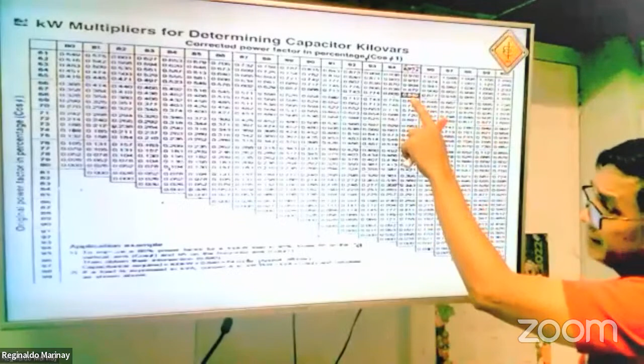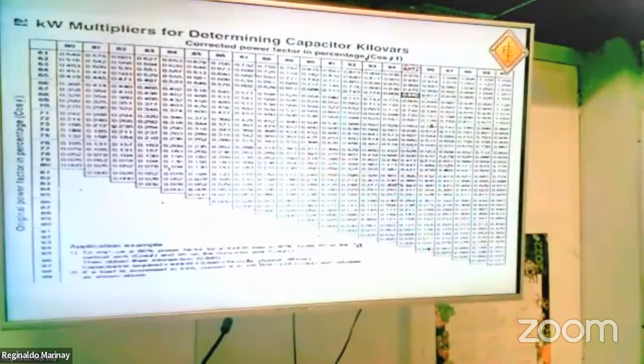Take a look here at this table, from 65% to 95% power factor. You will see here this is 0.84 actually. The beauty of this table is that it gives the difference of tangent theta old minus tangent theta new. Of course, that is very useful if you have this table, especially in your work. But if you have a scientific calculator, you can manipulate and calculate the value directly. Anyway, if you have that table, that's very easy, right? So we have QC equal to 0.84, so 84 kVAR. That will be the value.